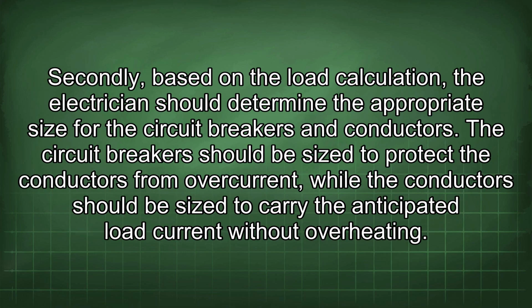Secondly, based on the load calculation, the electrician should determine the appropriate size for the circuit breakers and conductors. The circuit breakers should be sized to protect the conductors from overcurrent, while the conductors should be sized to carry the anticipated load current without overheating.